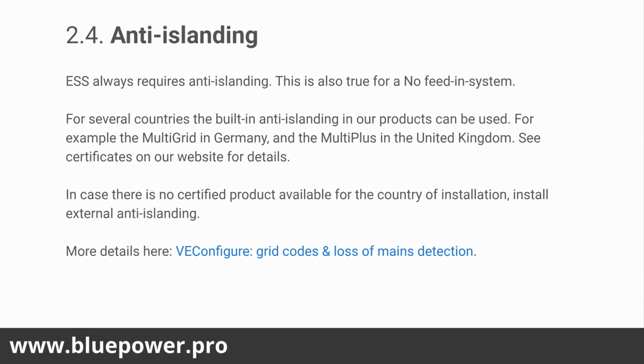They will never be compliant because they only have one contactor, so it is required to have an external anti-islanding device. Those devices aren't intended for our specific use cases for anti-islanding, which requires 2 contactors. So the Multiplus-IIs have 2 contactors in series, whereas the older Quattros or Multiplus inverters only have 1 contactor, and that doesn't comply with the requirements. So for that, you can get the anti-islanding box that is available from Victron Energy.